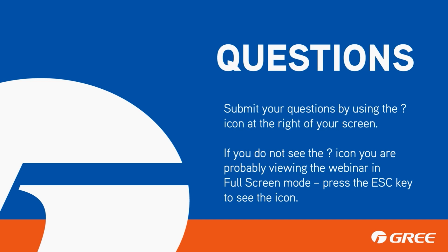All right, next one is from Rocky. Can the system be used with zoning controls like Honeywell? Okay, that's a good question. So, you want me to answer that? Sure. So the answer is yes. The main thing we want to make sure is we're not exceeding 0.5 static. We want to be sure to have a dump, not a bypass.